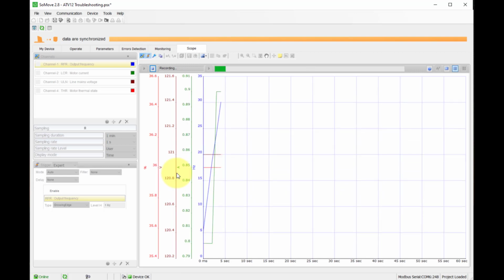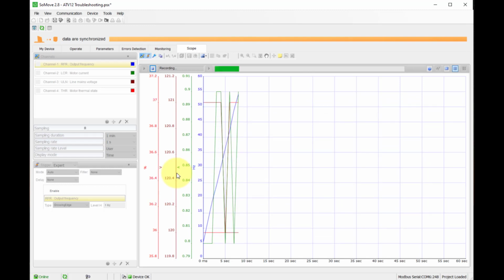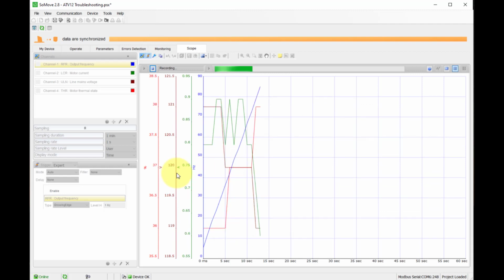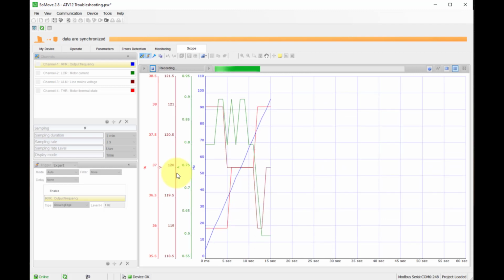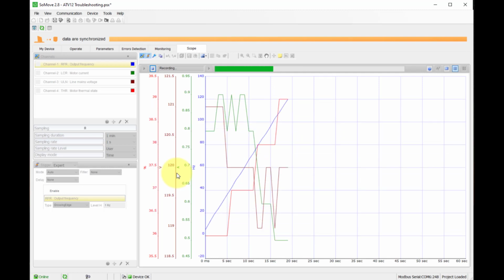And we're on a 10-second ramp, so the blue trace will take a little while to ramp up, and it's going to ramp all the way to 120 hertz, so you'll see it auto scaling. And once the frequency hits 60 hertz, as we saw in the last trace, the current will start to drop because the inductive reactance in the motor is increased. Therefore the current will start to decrease, therefore the torque will go down.